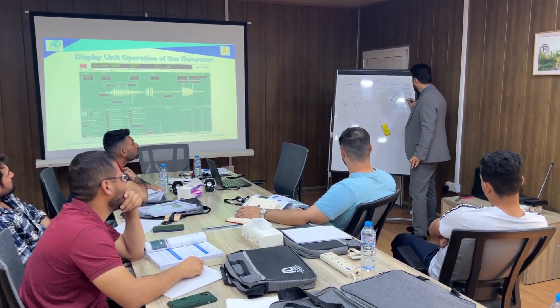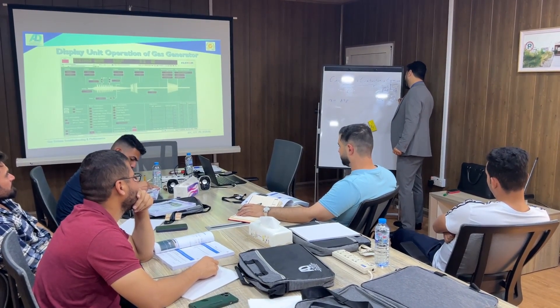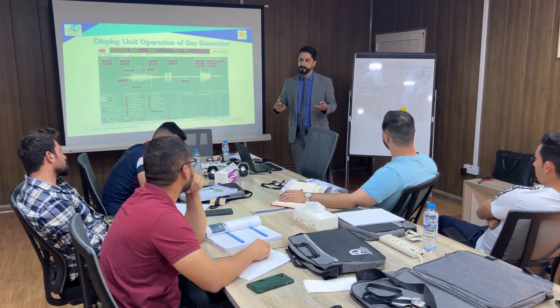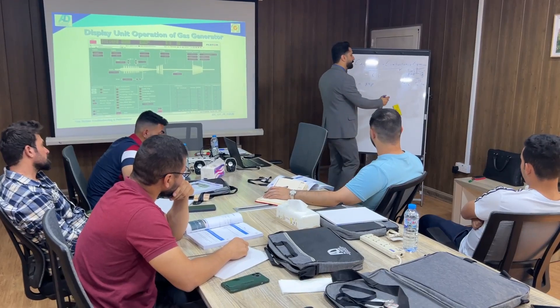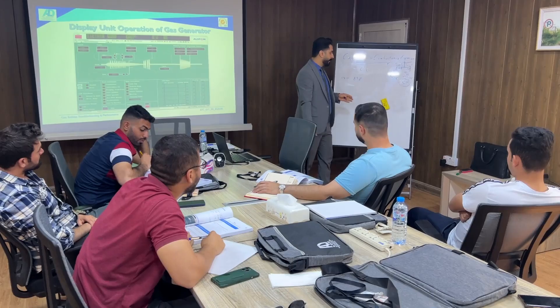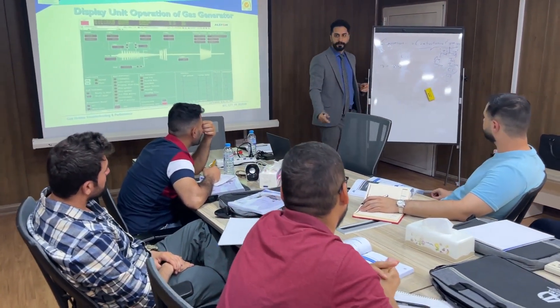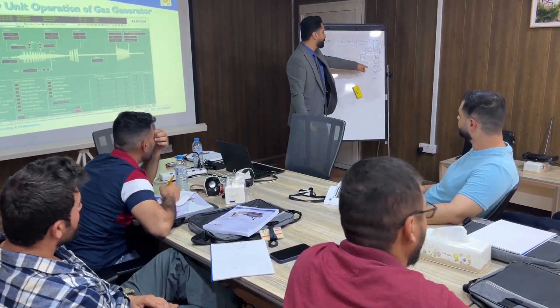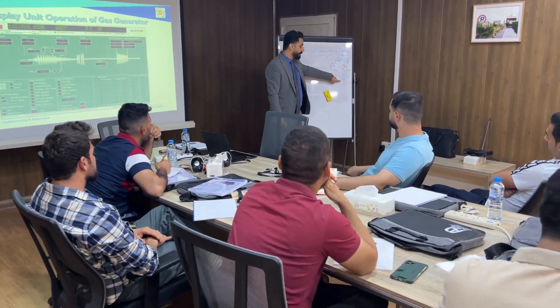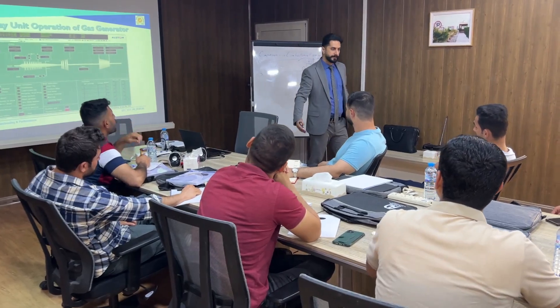But in dual shaft, we are going to have two turbines. In different gas turbines, we can find different names, but the most common is that we call one of them CT, which is compressor turbine, and the other one PT, which is power turbine. So we are going to have one compressor turbine for rotation of the compressor, and the other one is coupled to the facility which is going to be used for power generation.